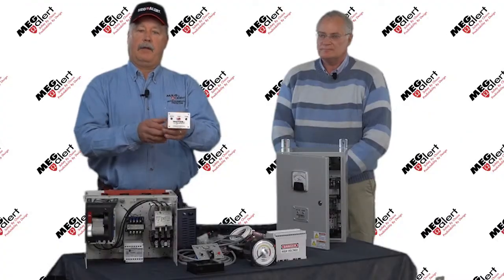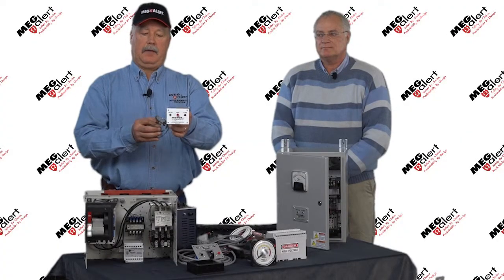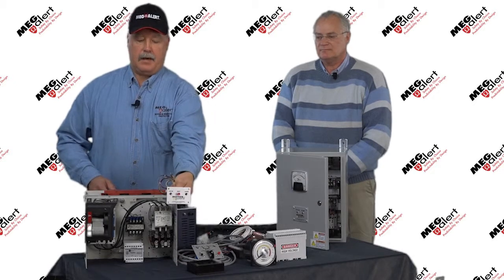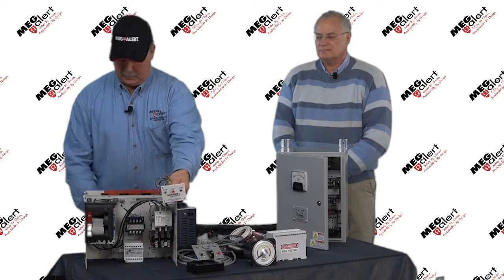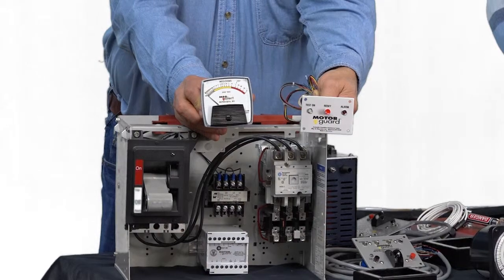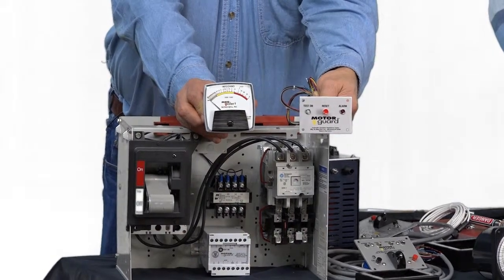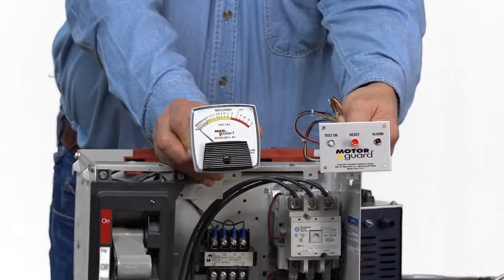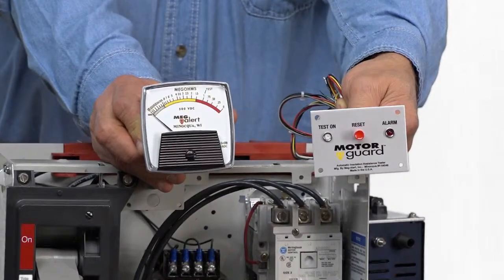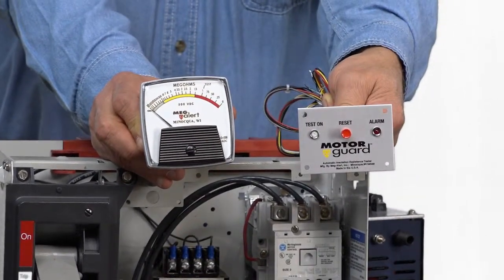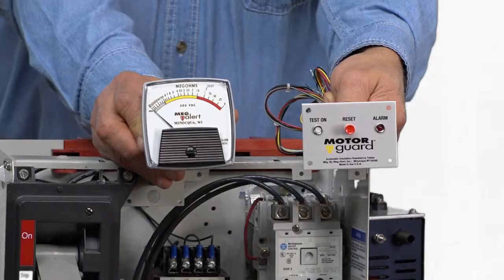It comes with a remote LED cable or plate with a cable on the back that ends up mounted on the door of the cabinet, along with the megohm meter itself, which is the color-coded dial giving you the megohm value, as well as a user-friendly green, yellow, red zone, so people can understand if the motor is starting to deteriorate.